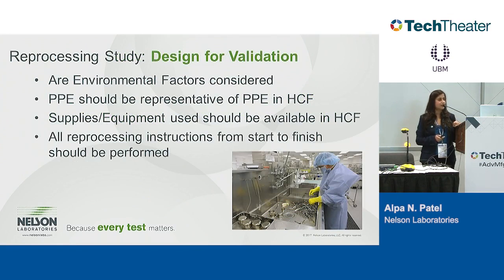When you're designing for validation, you want to consider environmental factors, and the PPE that's used in the central processing that the validation unit will wear as well. Supplies and equipment used should be available in healthcare facilities. A lot of times they specify you need to use this brush. If you can't provide it with your device, then you have to provide information on where they can purchase it and where they can buy that brush from. And all the reprocessing instructions have to be completed from start to finish. You can't pick a certain portion of the reprocessing instruction and say just validate this portion, and that should suffice for everything else. The entirety has to be validated.